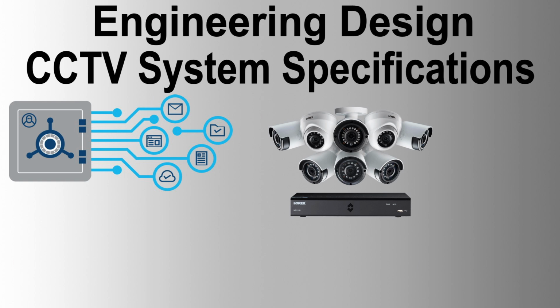Camera housings. All cameras located in hazardous areas shall have Ex-proof, Ex d, camera housings, and cameras located in non-hazardous areas shall have non-Ex-proof housings with ingress protection of IP65 as a minimum. Cameras located at sea stations shall have IP67 housings to protect against very high waves of the sea environment and all sea weather conditions. The housings shall have thermostatically controlled or PTC-controlled anti-condensation heaters and shall have protection against lightning and electromagnetic interference.